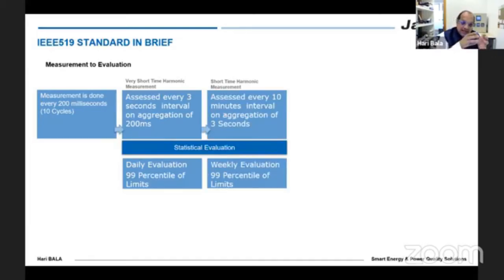The second option is that the 3-second data is assessed over a 10-minute interval and aggregated, and then that is used for weekly evaluation of the 99 percentile for the limits. So you can understand that one way is daily evaluation, and another is weekly evaluation, and they have given a 99 percentile limit specified in the table. It also says another way: the same 10-minute interval over a week is also assessed against 95 percentile limits. So there is a limit for daily evaluation at 99 percentile, a limit for 99 percentile for weekly evaluation, and a limit for 95 percentile for weekly evaluation.